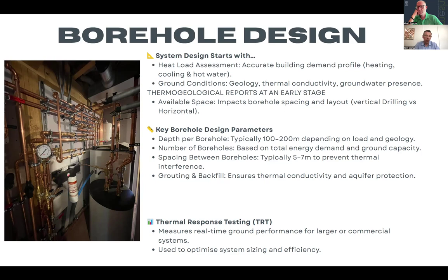you might need more electricity to run the heating system, and you would get less, you extract less from the borehole. So then you compensate with electricity to generate the same, let's say, 15 or 20 kilowatts heating output. But you're typically designing these so that those performance losses are minimized.